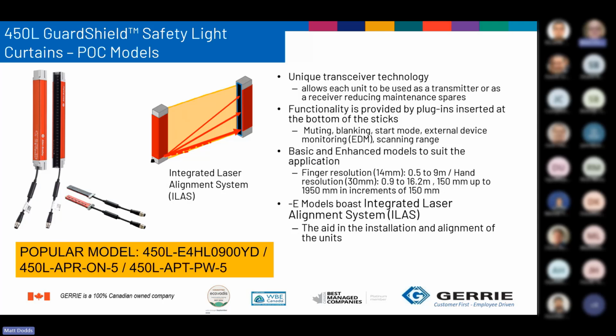The 450L GuardShield offers a unique transceiver technology. Each unit can be used as a transmitter or receiver, reducing maintenance spares. Functionality is provided by the plugins at the bottom of the sticks, and you get various functions there, so muting, blanking, start mode, external device monitor, and scanning range can all be changed. There are basic or enhanced models, in 14 and 30 mil resolution. The enhanced models give you access to more advanced features like blanking and muting, and they also feature an integrated laser alignment system, which aids in installation. The most popular model is the enhanced version in a 3-foot length.